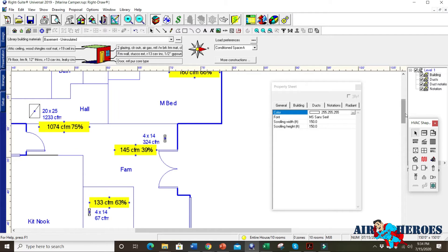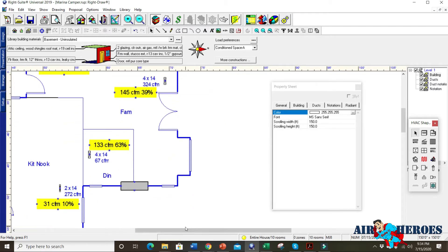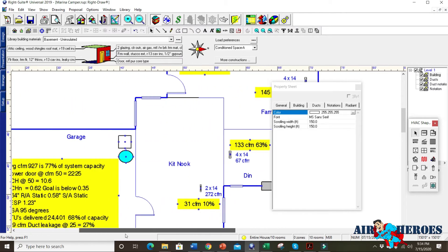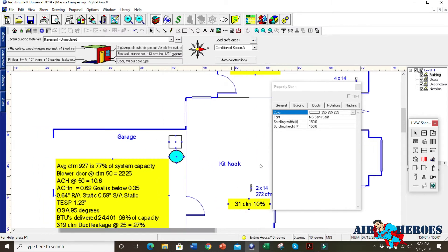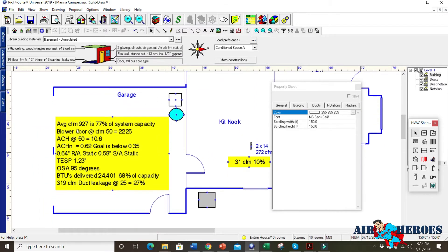So you can talk intelligently and know what a guy's talking about and he's just not baffling you with bullshit. So let's go down and look at what we actually measured. So the average CFM is 927. It's supposed to be 1200. That's 77% of capacity.